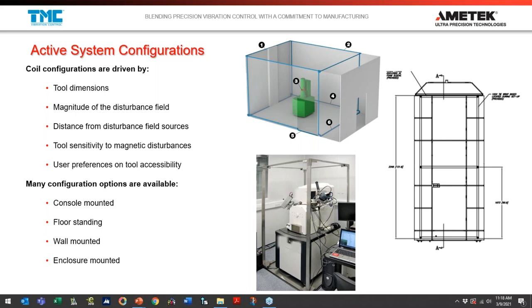Let me talk about configurations because there are many ways to configure these coils depending on application needs. One example shows a scanning electron microscope in a room with Helmholtz coils mounted in a six-sided box on the walls — a very common configuration to get a large cancellation volume in the area of the scope. If you can't mount things on walls, we can do cages that mount on the floor to also create six-sided boxes of Helmholtz coils. We can even mount them inside enclosures — for example, a transmission electron microscope roughly 12 feet tall with a coil set mounted inside.